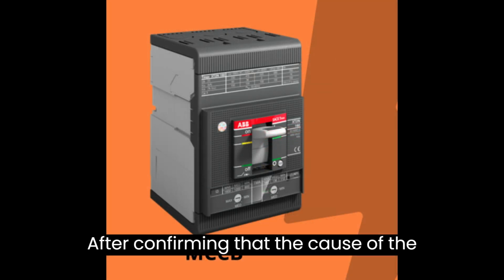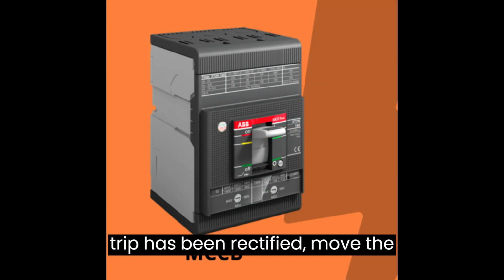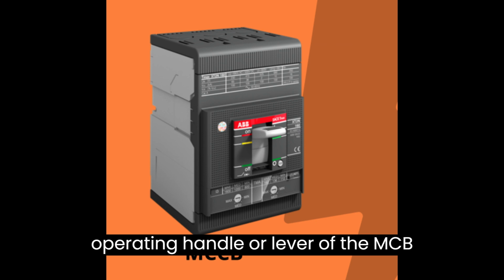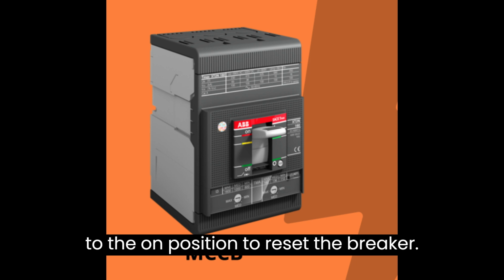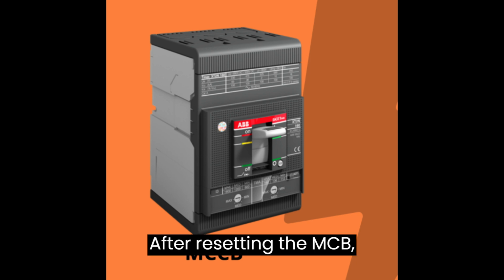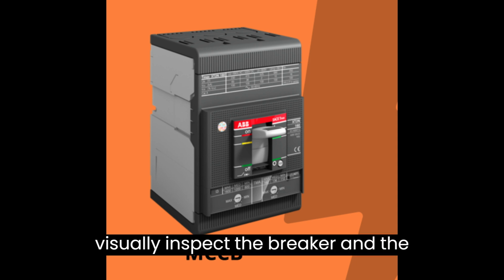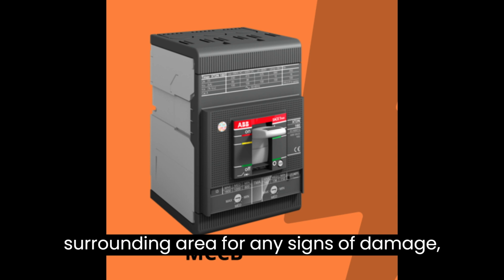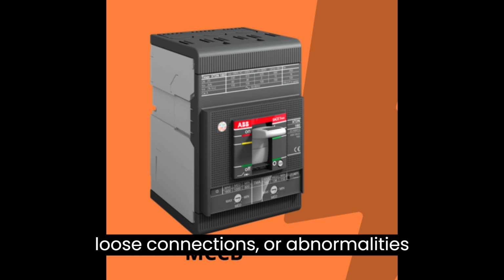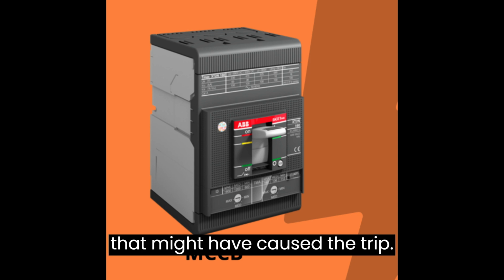After confirming that the cause of the trip has been rectified, move the operating handle or lever of the MCCB to the on position to reset the breaker. After resetting the MCCB, visually inspect the breaker and the surrounding area for any signs of damage, loose connections, or abnormalities that might have caused the trip.